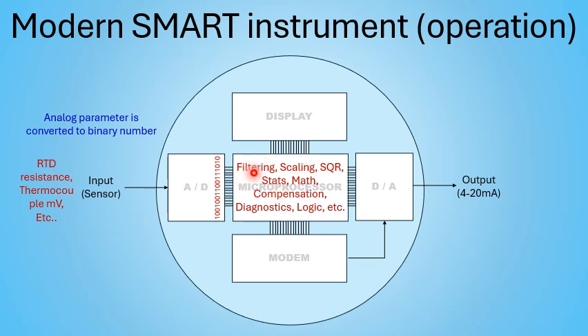That microprocessor does all of the filtering, the scaling, basically your URV, LRV, etc. Sometimes it'll do square root extraction. It can do statistical things like averages, moving averages, mean, max, min. It can do various math like finding the difference between two RTDs, finding the sum of two different process variables. It can do compensation as temperature changes, etc. It can do diagnostics, really powerful diagnostics. Some of these instruments are not even doing a fraction of what they could and should be doing at most facilities. And they can even do logic and so forth. The power is pretty incredible.